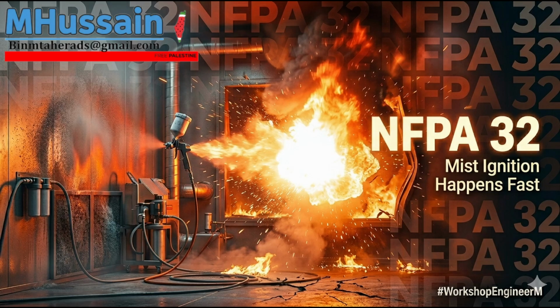That's even worse. The vapor recovery systems are calibrated to the specific boiling point and condensation temperature of the original solvent. If the new solvent has a different thermal profile, the condenser simply won't capture the vapor. And suddenly you have a highly explosive or toxic atmosphere bleeding into the workspace. Exactly. Which is why the notes explicitly state that for the 2004 edition, additional guidance and definitions were added specifically to better define and explain these machine conversions. They had to provide a rigorous framework for how to safely retro-engineer these systems. Or, I assume, forbid it entirely if the physics just didn't align.